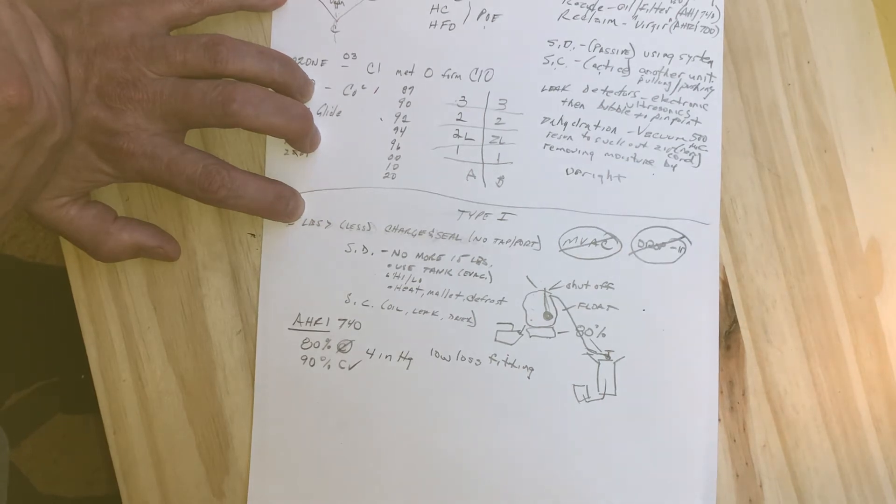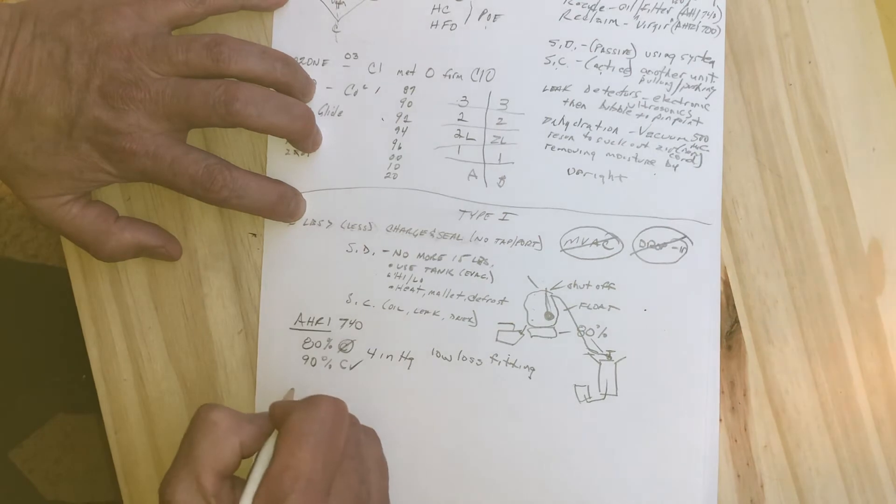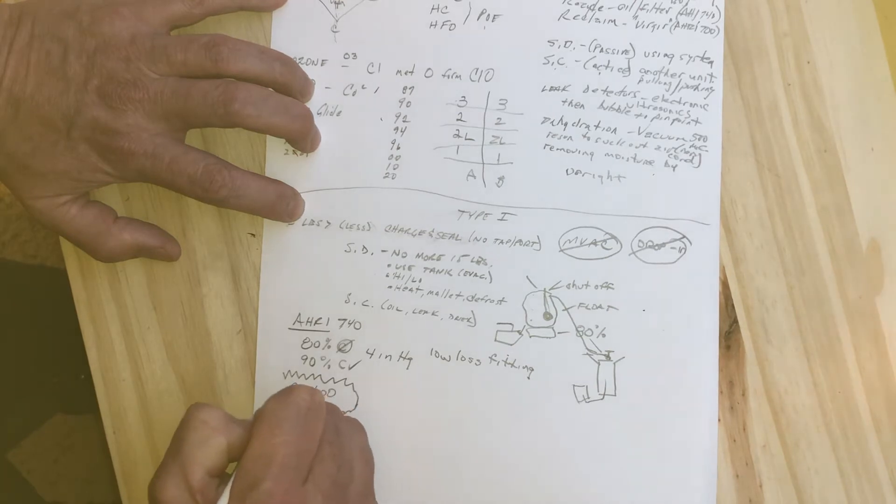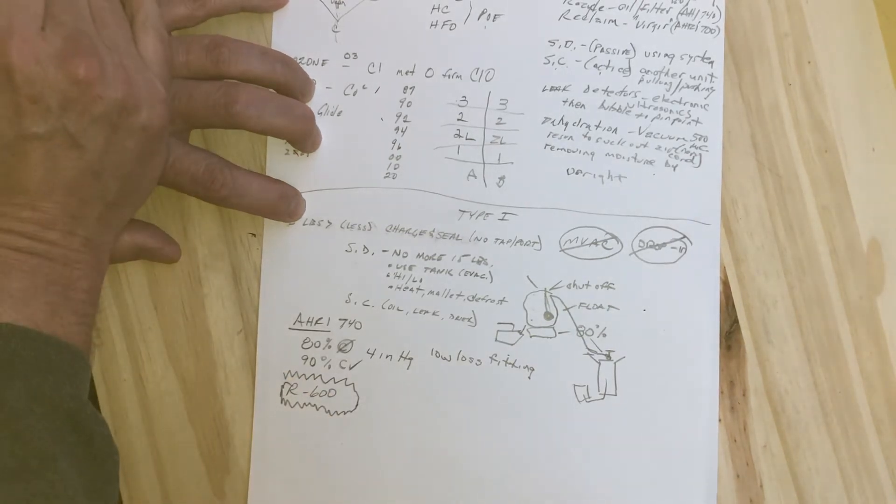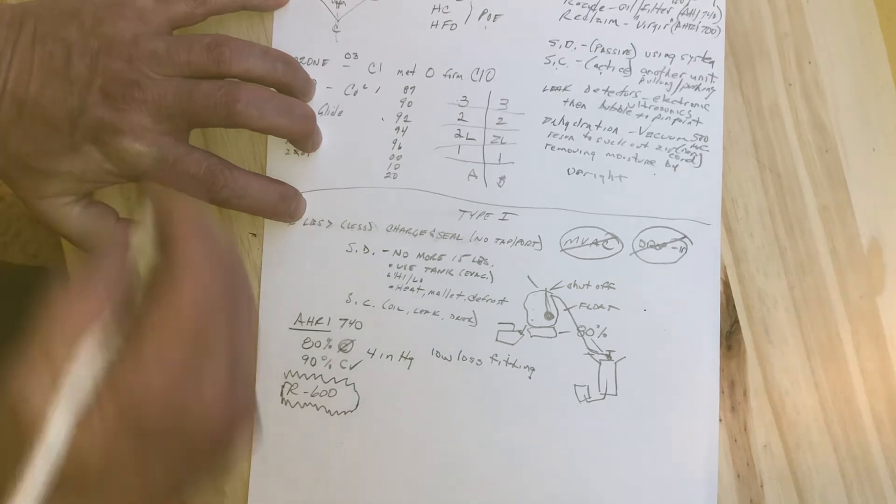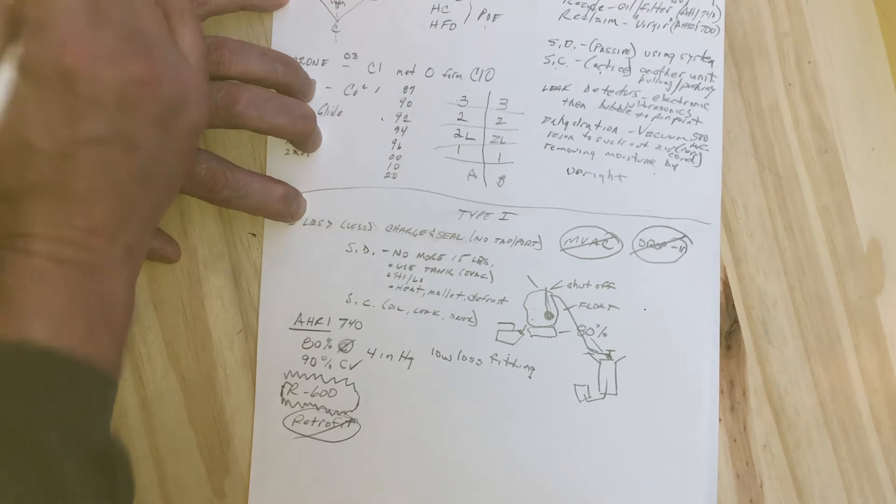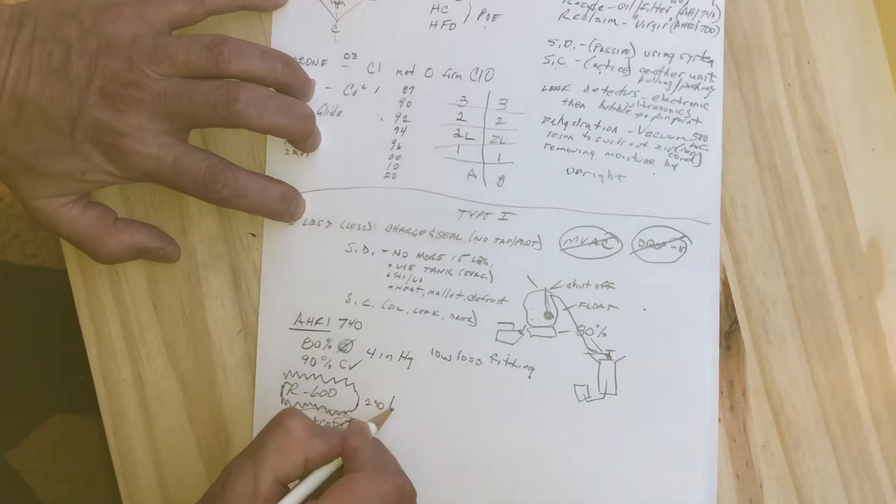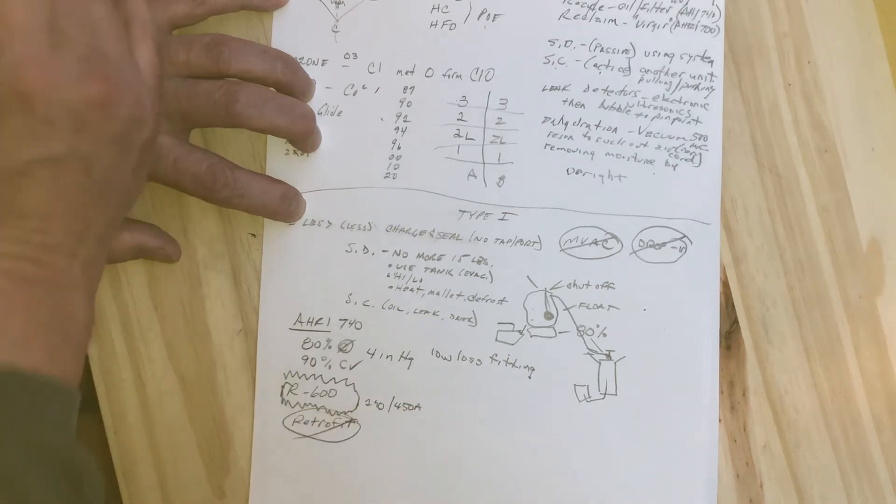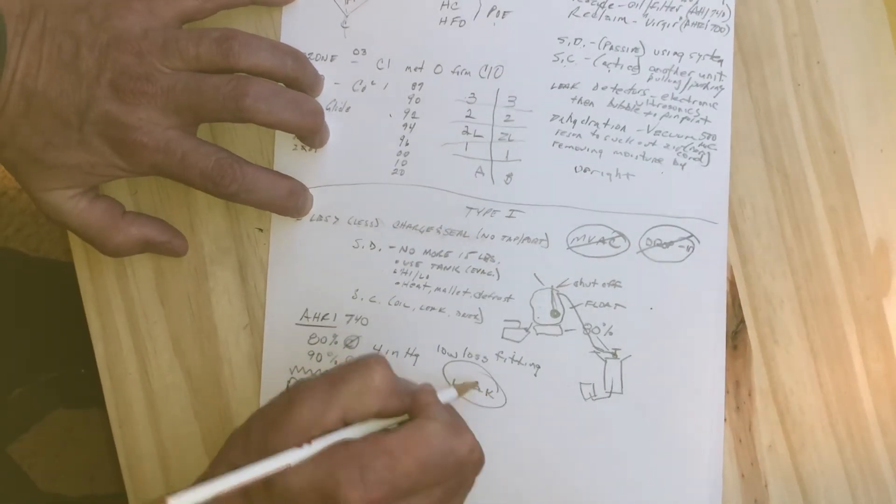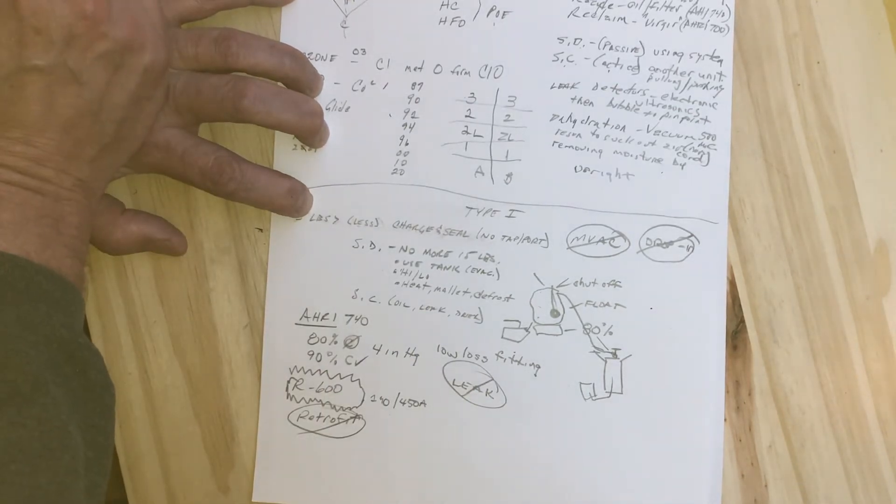If we have any R600, that's flammable. It's a hydrocarbon refrigerant, an A3 refrigerant that's highly flammable, and we can't retrofit with those. There's no retrofitting into that refrigerant. But they are being used along with 290 and 450A out in the field. The leak repair for that is going to be a little different than what we do for our regular stuff.